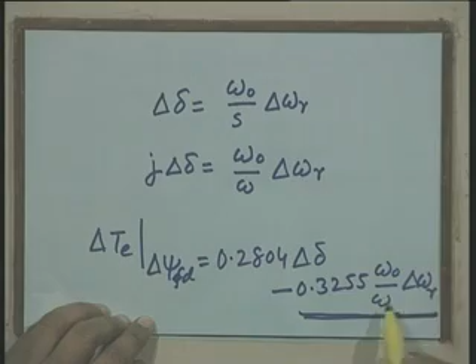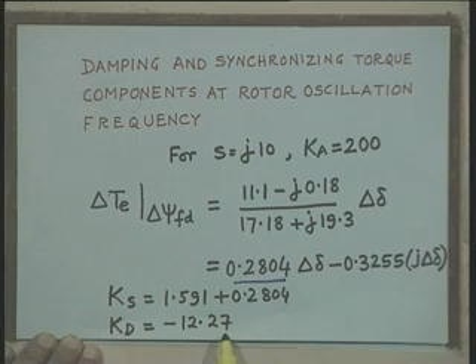Therefore, this coefficient is the coefficient of delta omega r. This is the total damping torque component, and this term 0.3255 into omega naught by omega becomes the damping torque coefficient. The damping torque coefficient is computed here and it comes out to be equal to minus 12.27. The important conclusion which we draw from this discussion is that when K5 is negative, if KA is taken around 200, it contributes to positive synchronizing torque coefficient and negative damping torque.